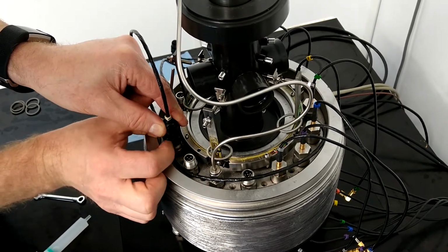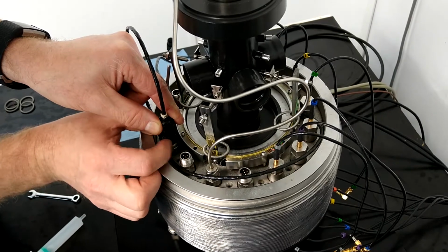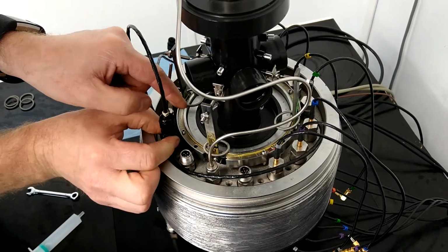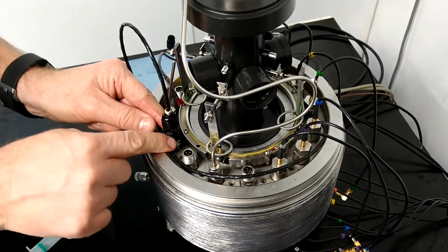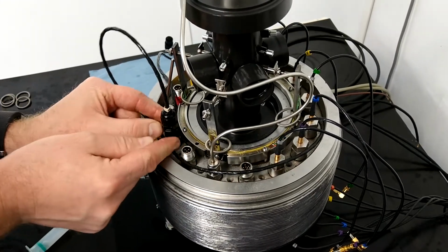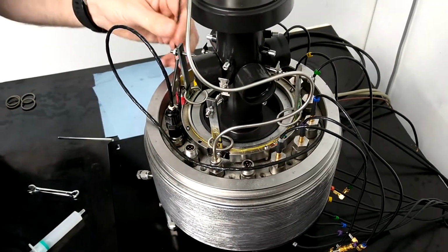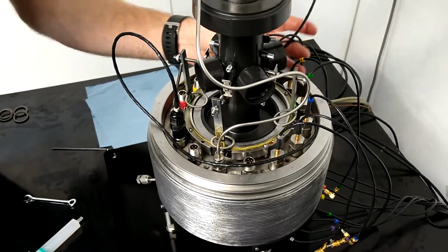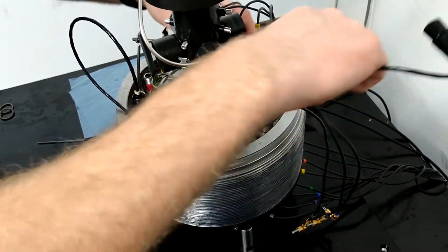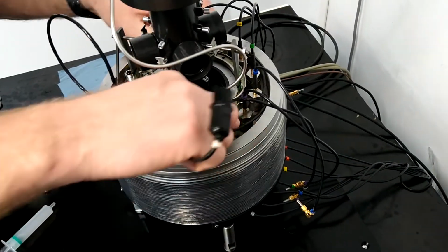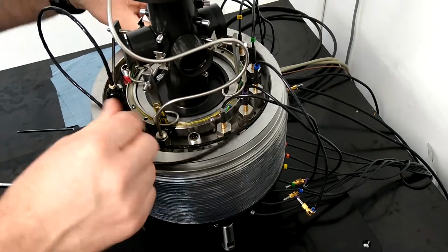When tightening the plug, only rotate the collar on the lower section. You may need to gently push down the fitting after a few rotations for this to fully locate at the bottom of the feed-through connector. Once fully tightened, it's advisable to loosen the collar by a quarter of a turn, as specific testing conditions can cause the plug to become difficult to remove when required.